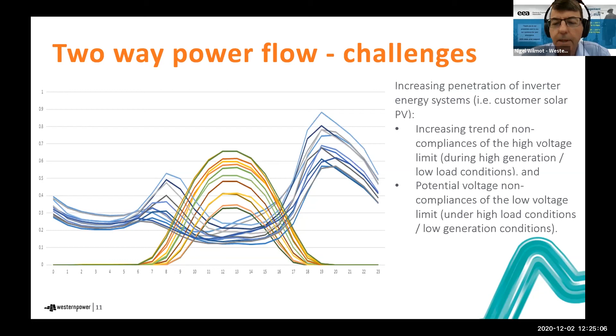So we've got several aspects to our strategy. From DER, and the two things on the left there, you can see network voltage rising as we get more and more distributed energy. Load is lighter on the end of the networks, and the source is flowing in the reverse direction, which is forcing our network voltage up. And then the other issue, with a decreasing proportion of inertial generators on our network, we have concerns about system stability going forward.